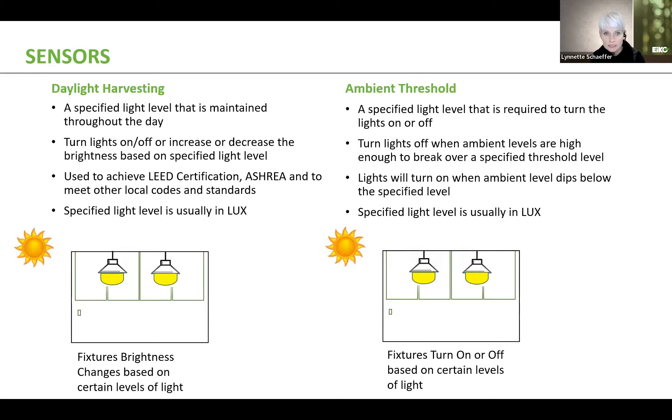Now, daylight harvesting is a form of a photo sensor or photo cell. It's slightly different in the fact that with daylight harvesting, which is used in a lot of commercial type applications where you have natural sunlight coming through the space, that sensor is programmed to look for a specified light level. It's up to the owner or the installer to state whatever that level needs to be. But basically, that daylight harvesting sensor maintains that specified light level throughout the day. So in this example, in the lower left hand corner, as the sun comes up, you're going to notice that the lights will dim down.